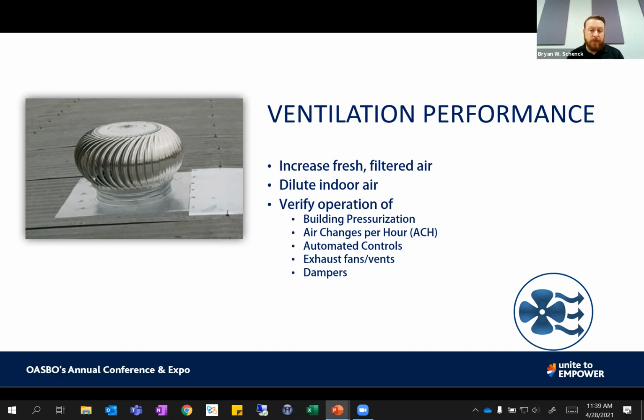Air changes is just a calculation of how much air is circulating in a room based on its square footage and volume - square footage and height - making sure so many air changes happen per hour. On the regular, you want 3 air changes; during a pandemic, you want 6 - we want to double that requirement. So 3 is good, 4 and 5 is better, but 6 is best right now given the environment we have.